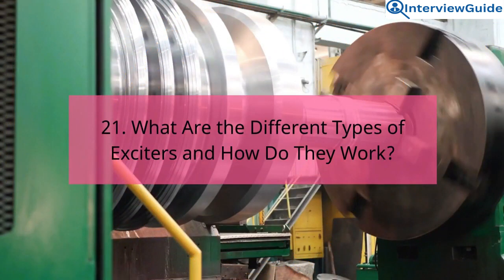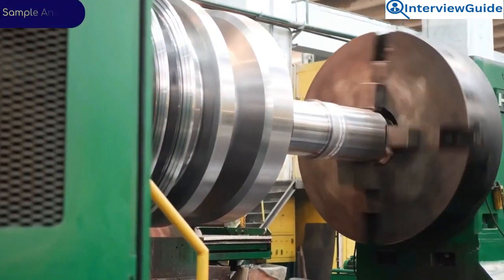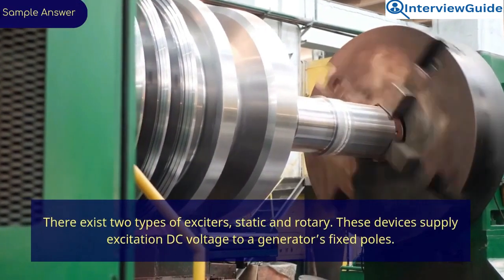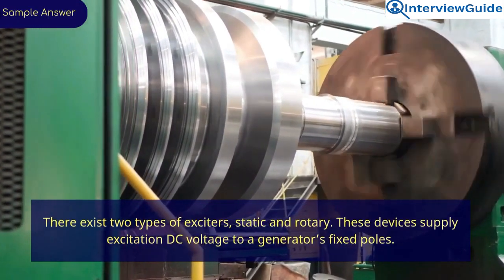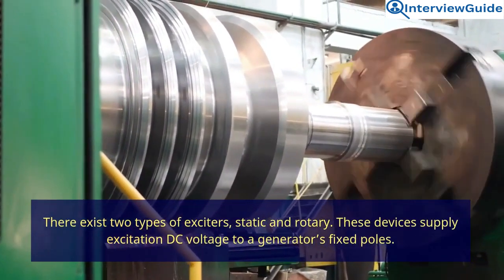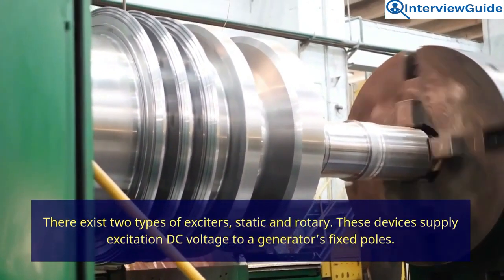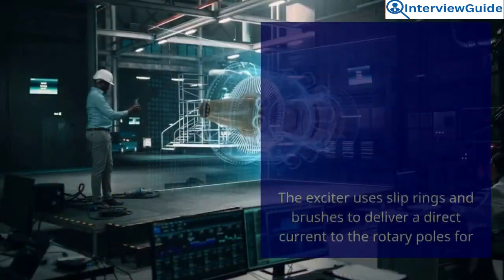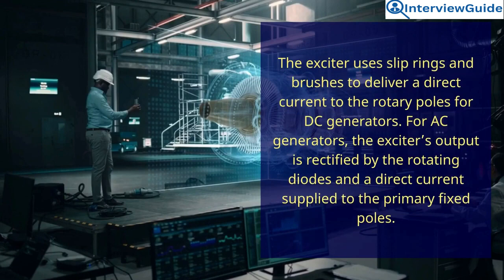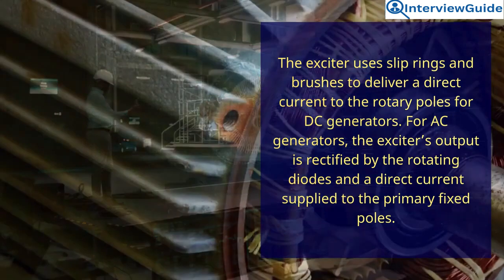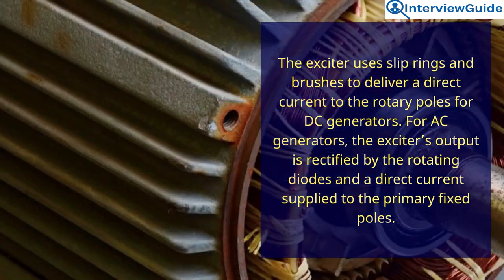21. What are the different types of exciters and how do they work? Sample answer. There exist two types of exciters, static and rotary. These devices supply excitation DC voltage to a generator's fixed poles. The exciter uses slip rings and brushes to deliver a direct current to the rotary poles for DC generators. For AC generators, the exciter's output is rectified by the rotating diodes and a direct current supplied to the primary fixed poles.